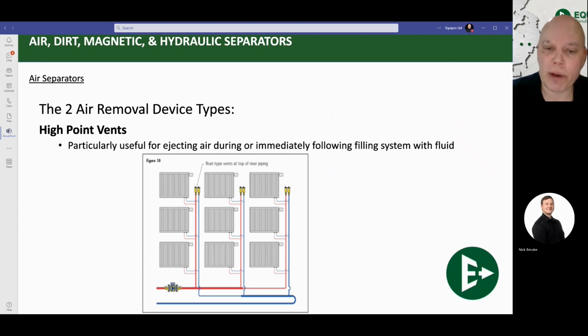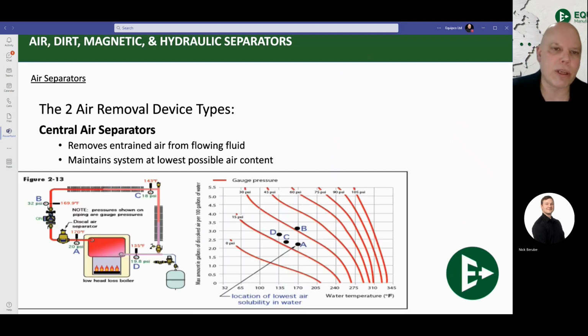The other type of air removal device that you can use, you still need to have it high efficiency because that's required by code, is your high point vents, where you put them at the highest point of a system. They're usually used for the original filling of a system, and then they're not really designed to burp out air exactly after that. They still can, mind you, like if you get a little air pocket that's released and it finds its way there, it'll still burp it out. But essentially, they're really just used for the filling of a system.